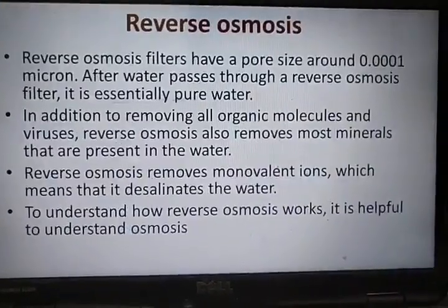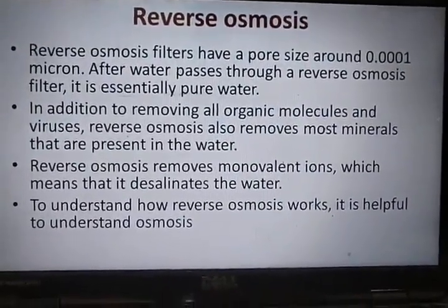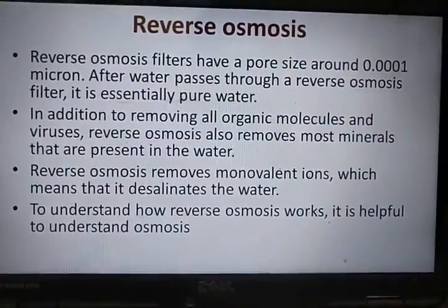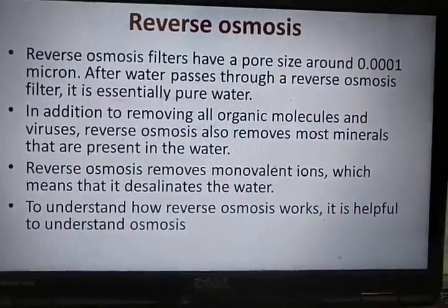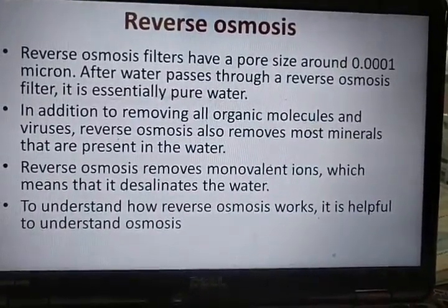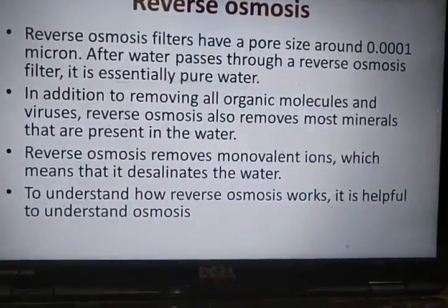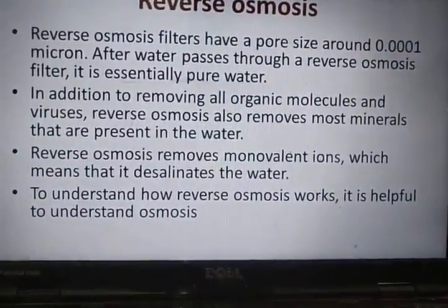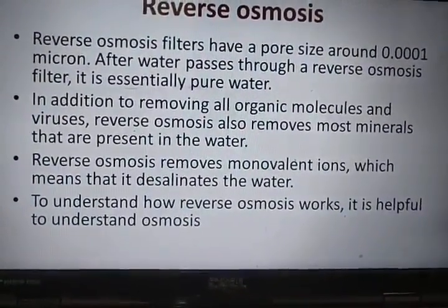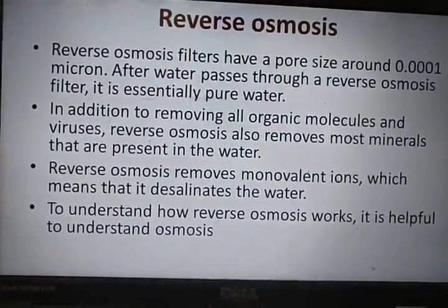Okay, then comes reverse osmosis. Reverse osmosis filters have a pore size of around 0.0001 micron. When water passes through a reverse osmosis filter, essentially it will be very pure water because it removes all the viruses and also most of the minerals which are present in the water. Reverse osmosis removes monovalent ions, which means that it also desalinates the water.